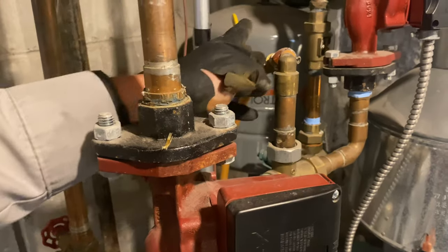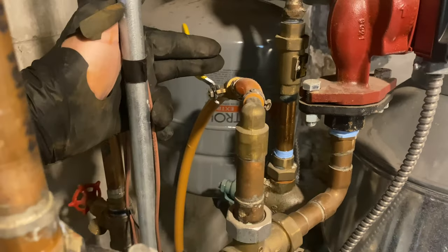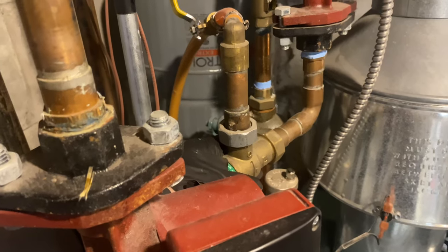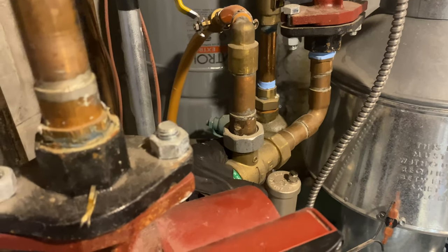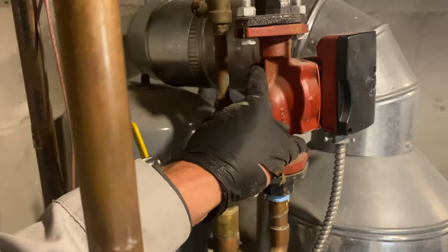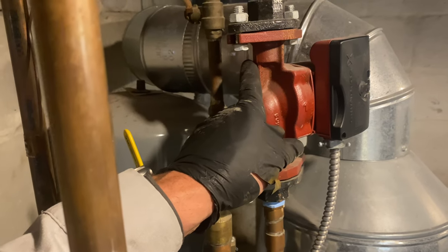So now this may need to be opened, because before it didn't matter, the boiler wasn't getting to 180 degrees. Now it's going to, right? And now you'll have a super hot floor. And if it's a wood floor, not a tile floor, the floor will be destroyed.